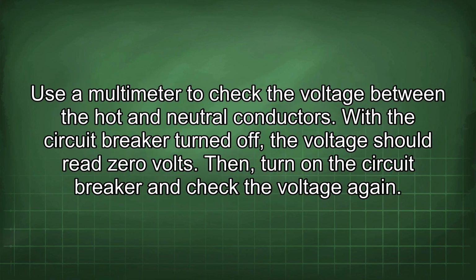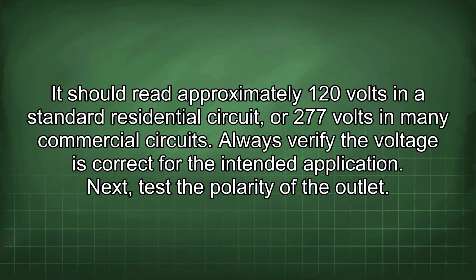Use a multimeter to check the voltage between the hot and neutral conductors. With the circuit breaker turned off, the voltage should read 0 volts. Then turn on the circuit breaker and check the voltage again. It should read approximately 120 volts in a standard residential circuit, or 277 volts in many commercial circuits. Always verify the voltage is correct for the intended application.